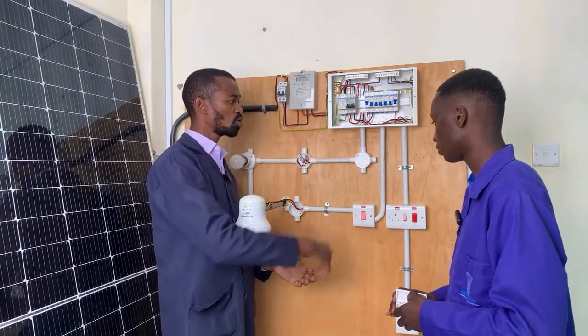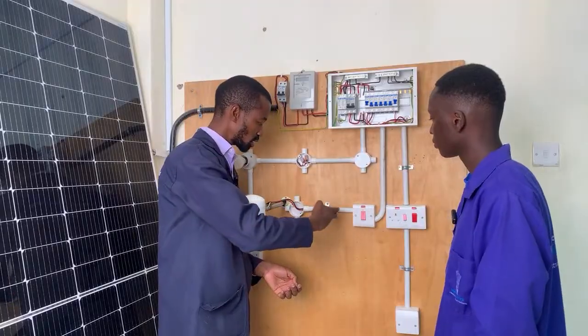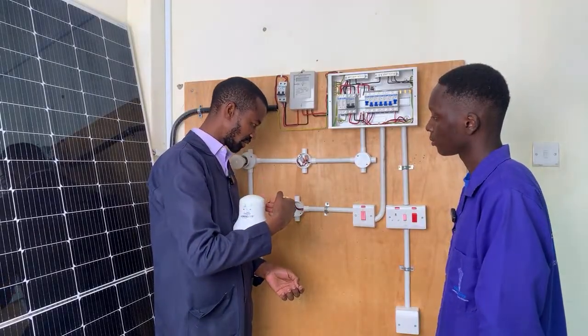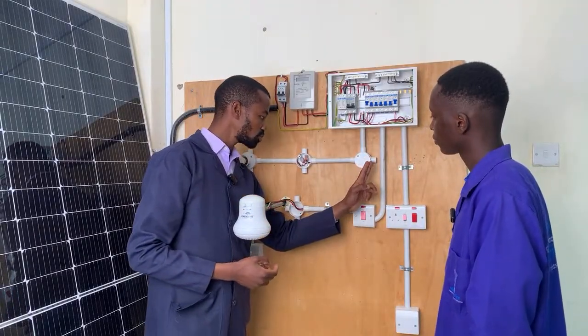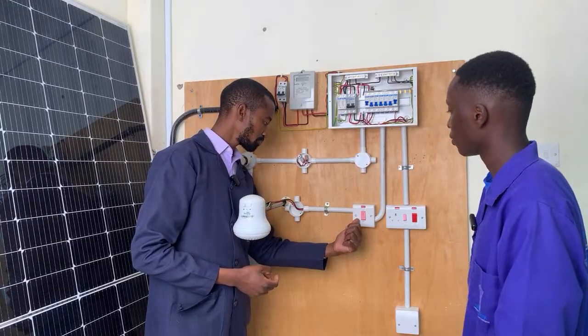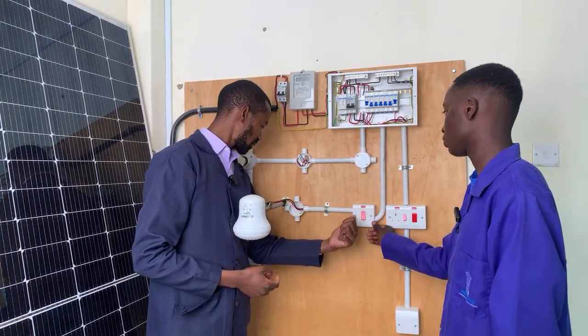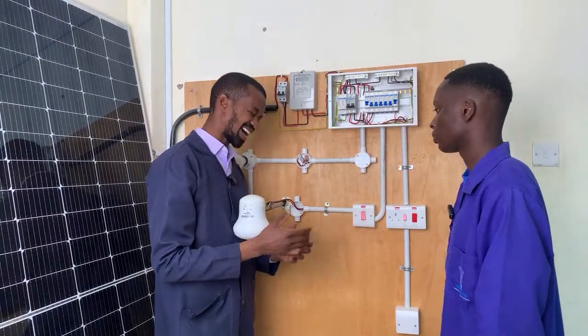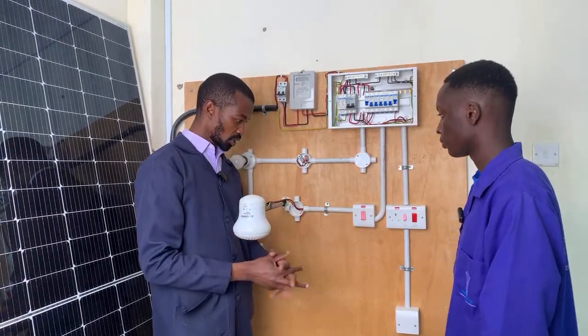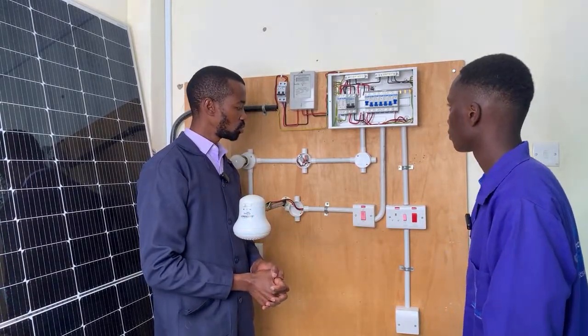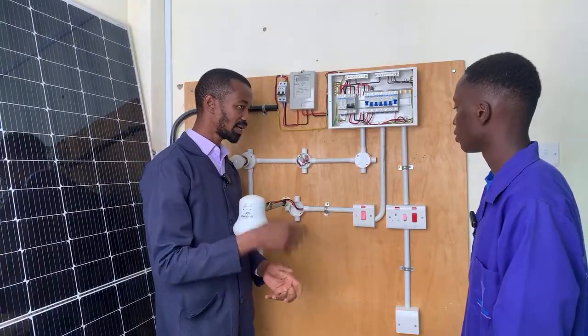We will replace the entire cable with a 4.0mm cable, running from the consumer unit to the switch, and then from the switch all the way to the instant shower head, it has to be 4.0. So the best thing we can do is start with wiring it.